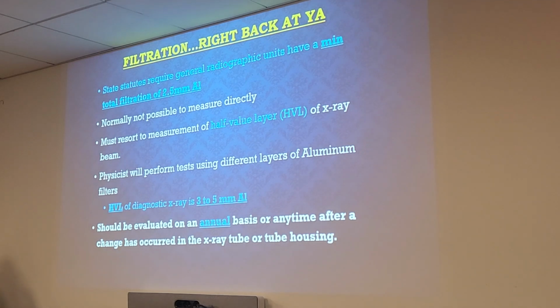So there is no actual way to measure the filtration directly, so what the medical physicist does is they measure the half value layer, the HVL, of the X-ray beam. Alright, so the half value layer for X-ray is 3 to 5 millimeters of aluminum, and filtration, of course, is tested annually.